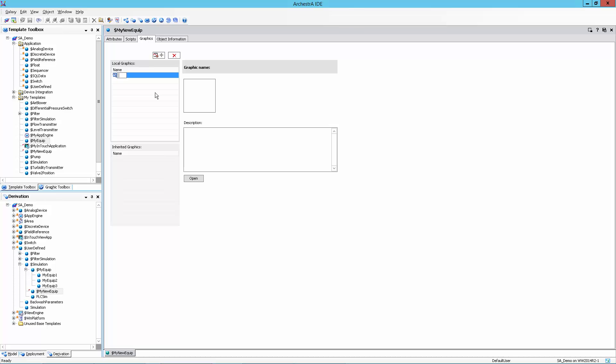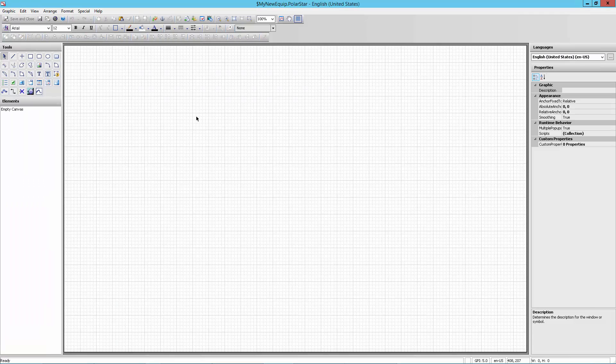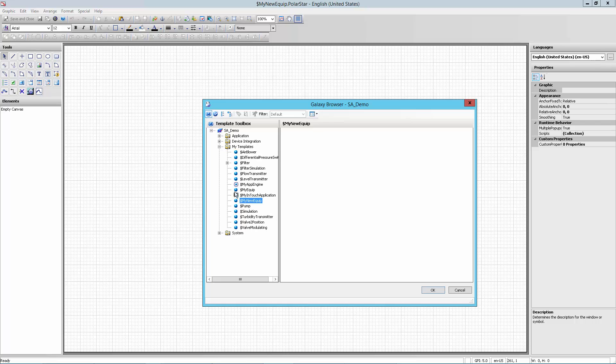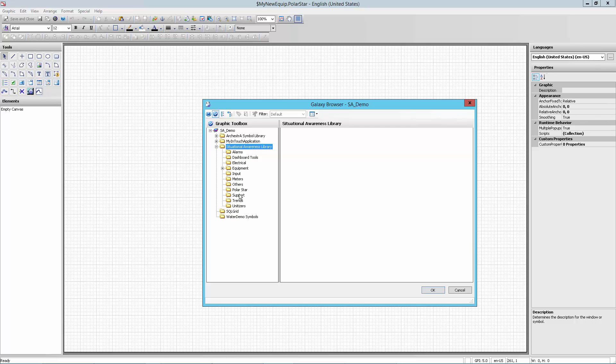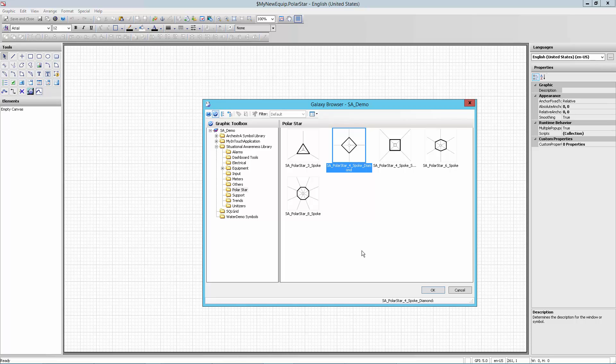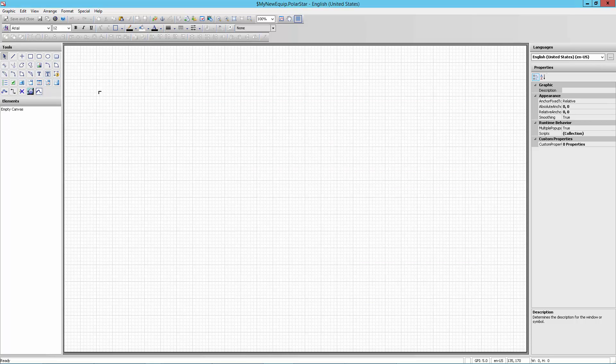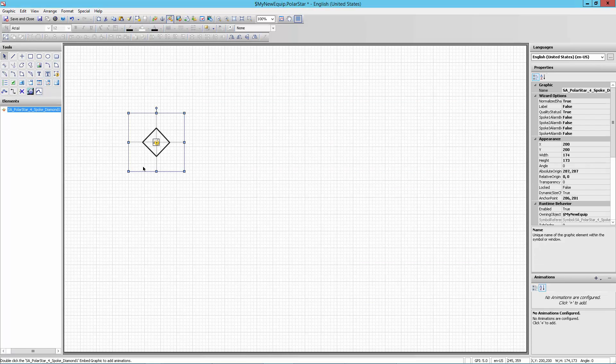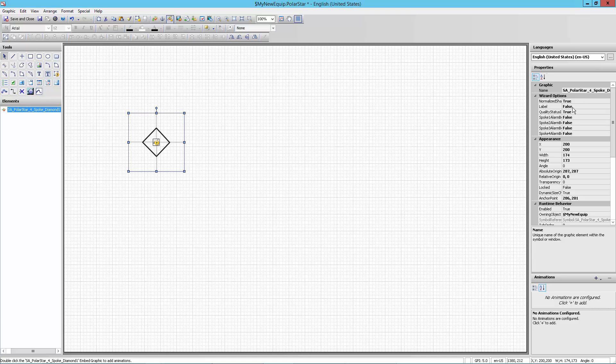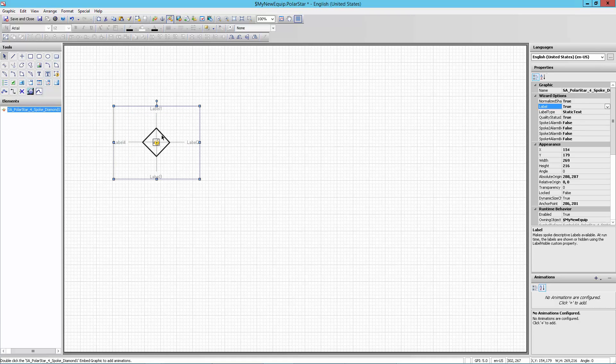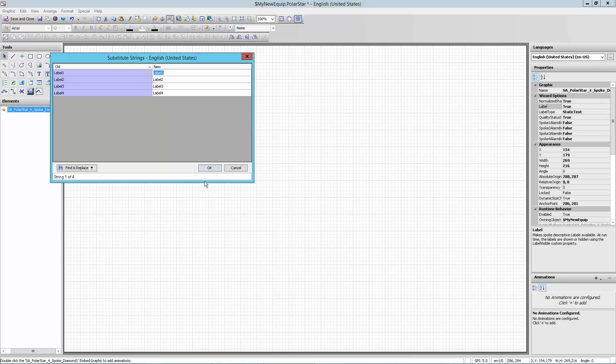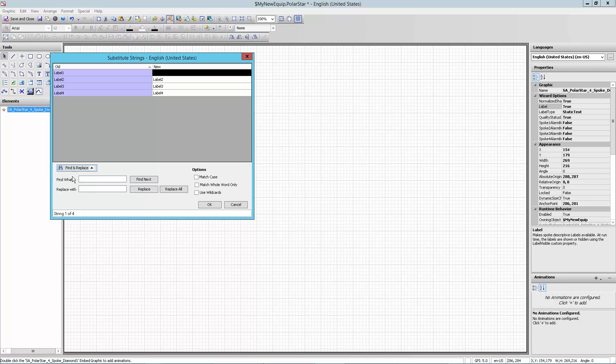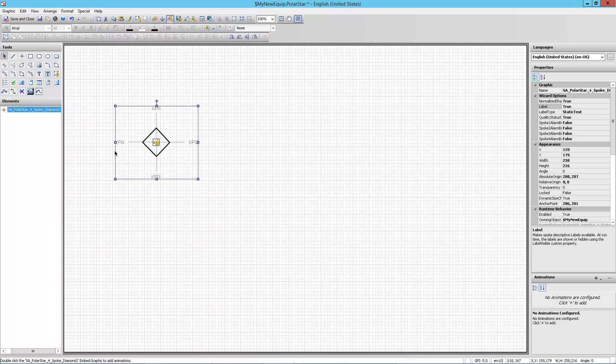What I really want to show here is I'm going to add the graphics. The graphics that make it possible to create that symbol and the faceplate. So I'm going to start first with my polar star symbol. I'll create that. And while I'm here, I'm also going to create my faceplate. I'm going to open the polar star and edit the polar star. So from here, the polar star in itself I've gotten out of the situational awareness library. So if I come over here to the graphic toolbox, go to the situational awareness library and go down to polar stars, I'm going to pick the four spoke diamond here and I'm going to drop it on the screen. I'm going to go over here and I'm going to turn on the labels so they can see them. I'm going to use substitute strings. Go over here to substitute strings to swap out all those labels for KPI. So I'm going to say label, replace that with KPI. Replace all those. Okay, so now I've got those labels there replaced out.